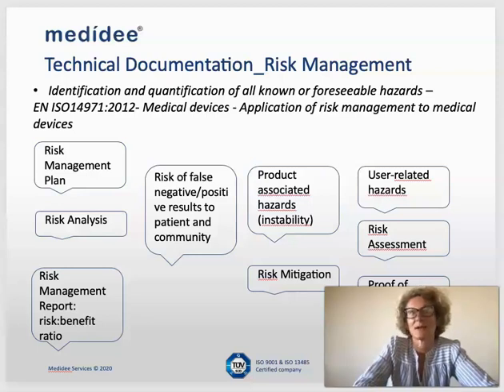Also, identify the risks associated with product instability or with the use of the product. Typically, if the test is very difficult to use, it may generate erroneous results, which may have an influence on the management of a patient. So this is very important to assess. Each risk identified during the risk analysis needs to be assessed, meaning that we need a scoring, which most of the time is based on the occurrence of the risk, the severity of the risk, and also the detection of the risk. We normally have a threshold. Based on this scoring, the legal manufacturer has to fix a threshold, and risks need to be mitigated. And of course, we need to have the documentation which proves the mitigation of those risks.